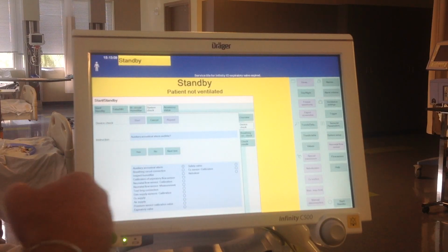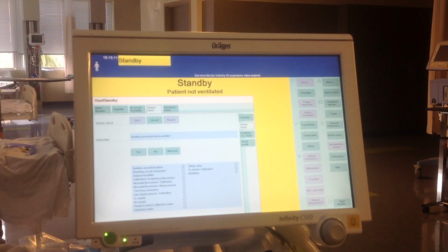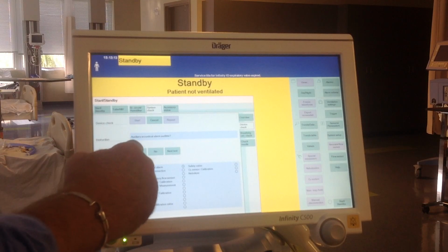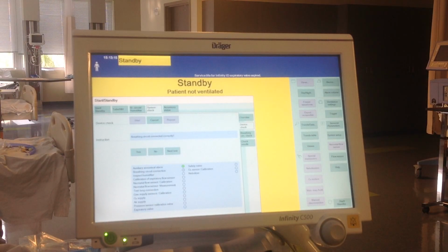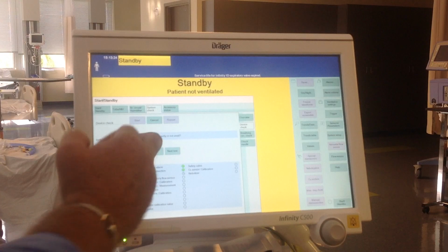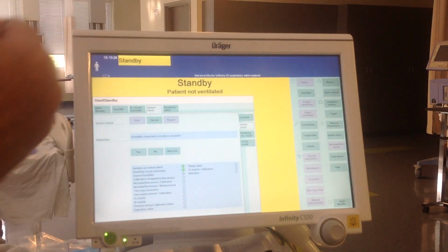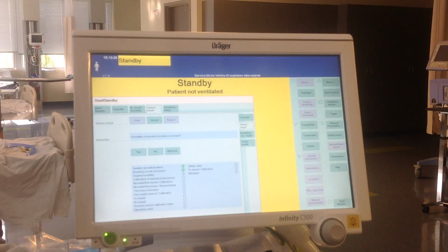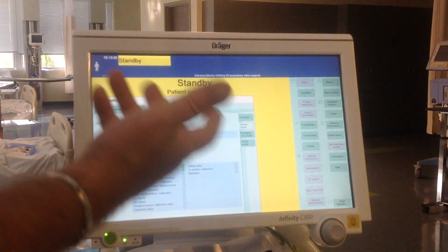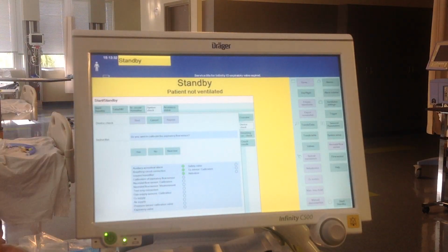Auxiliary. This asks me if I can hear that alarm. I'm going to say yes. Is the breathing circuit connected correctly? Yes. Humidifier connected correctly or not in use? If you're using an HME, you would have the HME in line at this time. So we're using an HME, we're going to say yes.